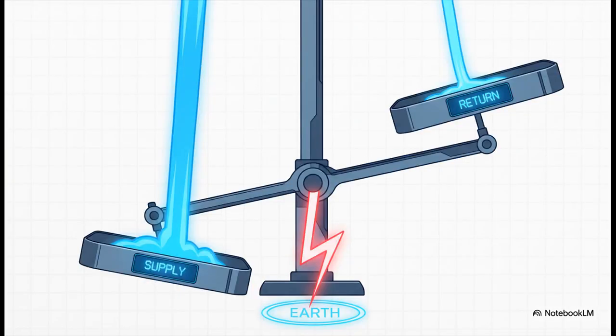Say the insulation on a wire fails. Or worse, a person touches a live part. Well, some of that current finds a new way to get to the earth. It literally leaks out of the circuit. And that leaked current, it could be flowing right through your body. The scale is now unbalanced. More current is going out than is coming back in.